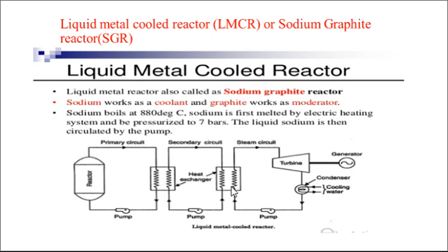In primary circuit, the heat absorbed by liquid sodium in the reactor, sodium becomes radioactive while it passes through the core and reacts chemically with water. So therefore, heat absorbed by sodium is transferred to secondary coolant known as sodium potassium. So initially here we are using sodium, then here we are using sodium potassium, and then there is a heat exchange between sodium potassium and normal water, light water. Therefore, heat absorbed by sodium is transferred to secondary coolant sodium potassium, NaK, in the primary heat exchanger, which in turn transfers the heat in the secondary heat exchanger called steam generator. And the steam is generated in the steam generator up to a temperature of 540 degrees Celsius for expansion in the turbine. So here it is sodium, here it is sodium potassium and here it is water.